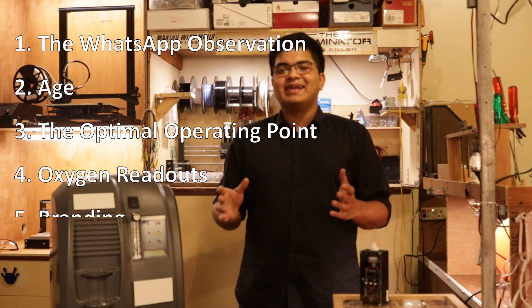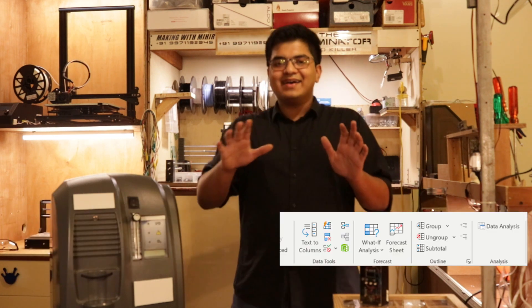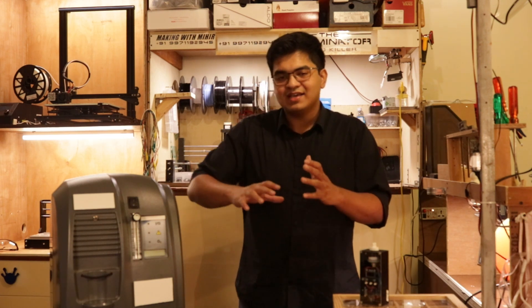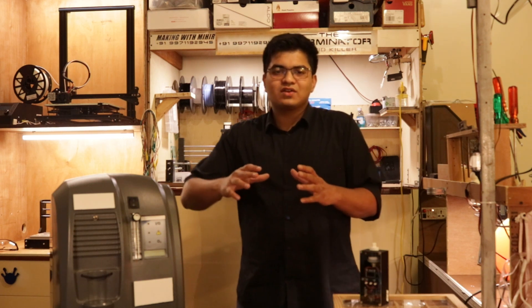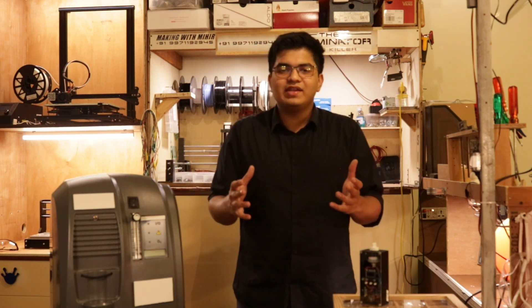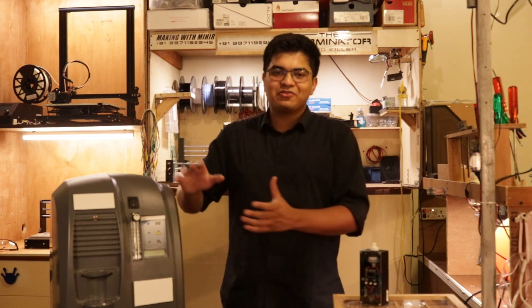Now, we have branding. I'm not mentioning brand names in the video because I don't want to get slapped with a defamation lawsuit, but also because it won't really help. I recently ran a t-test on some of these concentrators to see if statistically they behave the same way. The unfortunate thing I saw was that concentrators that looked exactly the same actually performed differently from one another. These machines are either made with a lower quality testing process or are probably all bought from the same factory, each brand buying them at different acceptable tolerances. So the little sticker on your machine means nothing, and neither does the form factor.